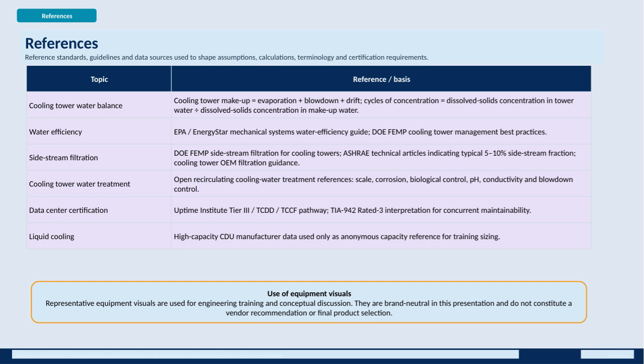These references cover a broad range of topics critical to water supply strategy, including seawater reverse osmosis desalination, direct liquid cooling, and cooling tower integration. Starting with the cooling tower water balance, the key factors involved are makeup water, which accounts for evaporation, blowdown, and drift. We also highlight the importance of cycles of concentration, which is a ratio of dissolved solids in tower water compared to the makeup water.